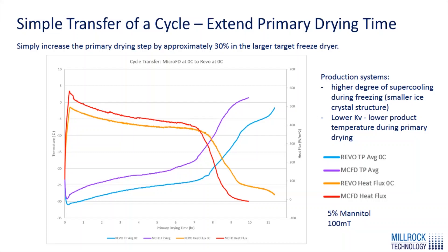Here we have a cycle dried in a MicroFD at 100 mTorr and 0°C for 5% mannitol, shown in the red line with corresponding product temperature in purple. That same recipe was run in a REVO lab-scale unit at 0°C, shown by the orange heat flux line and light blue product temperature. The REVO is drying at a slower rate with a lower heat flux and lower sublimation rate, taking about 30% longer to run. A safe way to transfer is to use the same cycle conditions and extend the primary drying time.